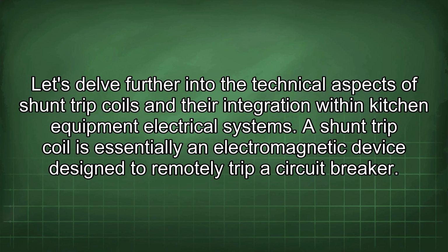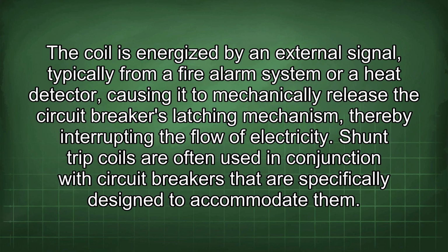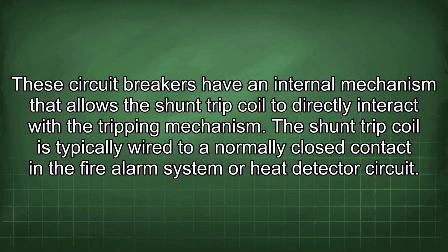A shunt trip coil is essentially an electromagnetic device designed to remotely trip a circuit breaker. The coil is energized by an external signal, typically from a fire alarm system or a heat detector, causing it to mechanically release the circuit breaker's latching mechanism, thereby interrupting the flow of electricity. Shunt trip coils are often used in conjunction with circuit breakers that are specifically designed to accommodate them. These circuit breakers have an internal mechanism that allows the shunt trip coil to directly interact with the tripping mechanism.